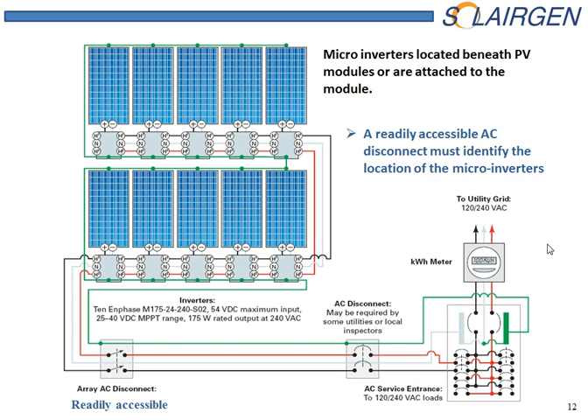For the AC side, microinverters located beneath the PV modules, which is where they typically are, must have a disconnect. Of course they do. But it's a non-load rated disconnect. That being the case, there has to be another readily accessible AC disconnect located with a label on it stating where these inverters actually are.